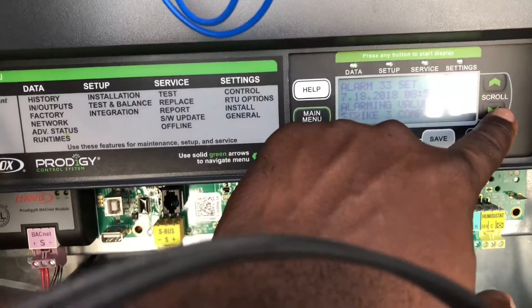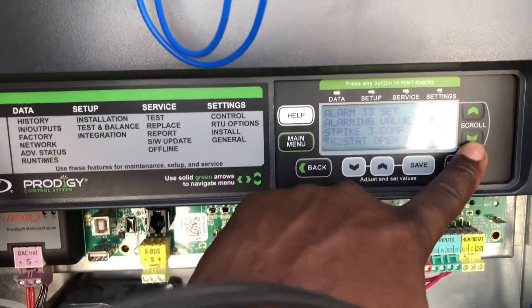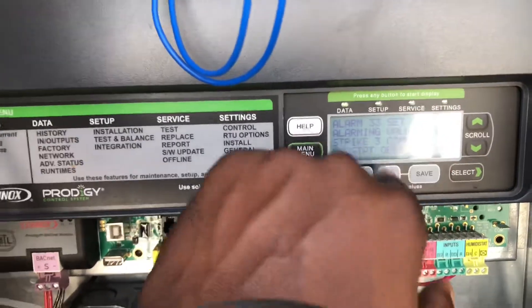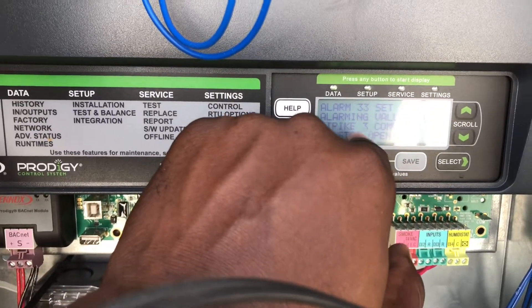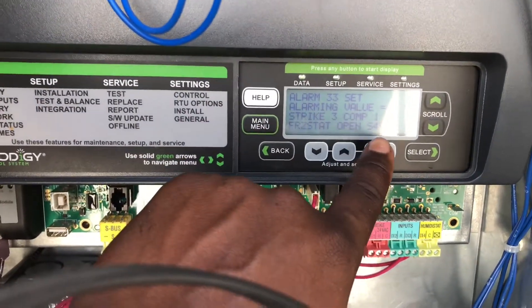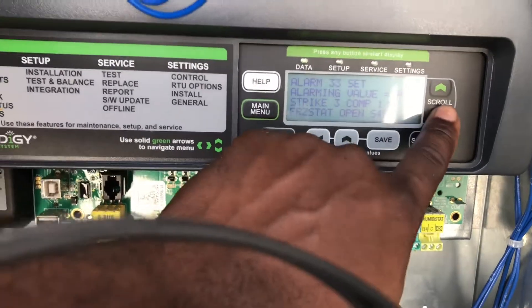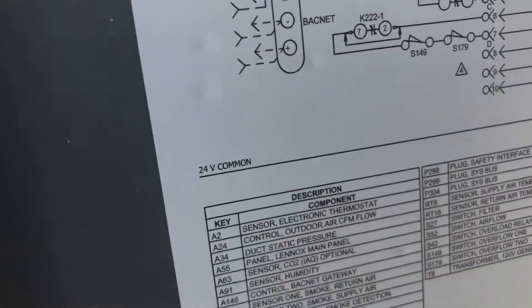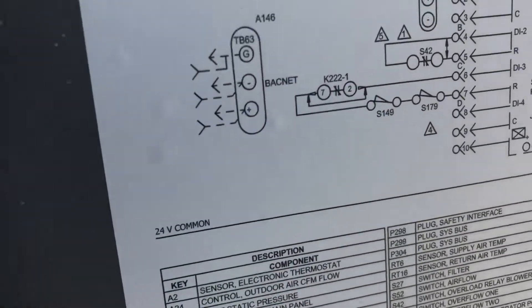The alarm went off and it had three strikes on the compressor, and it even gives you the problem with the unit itself. It says freeze stat open, S49.